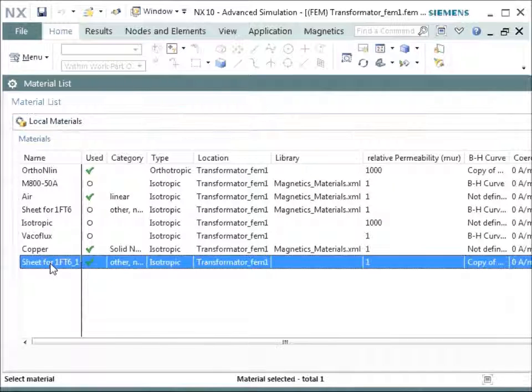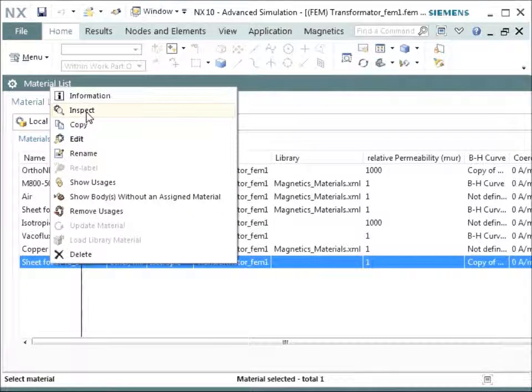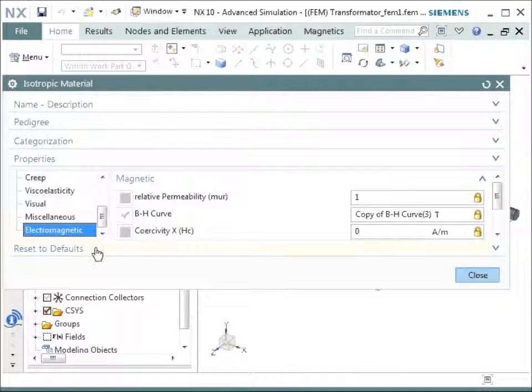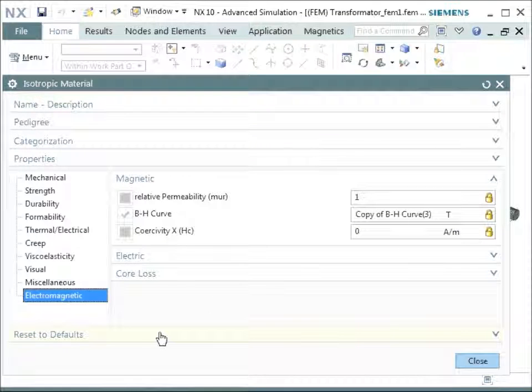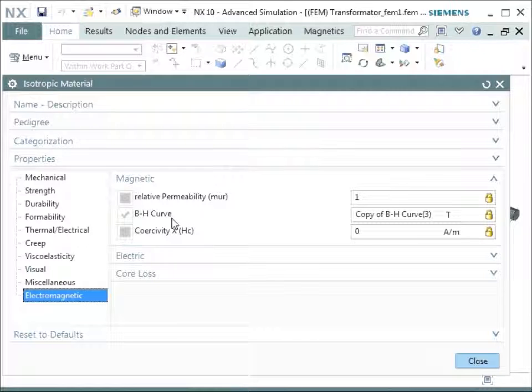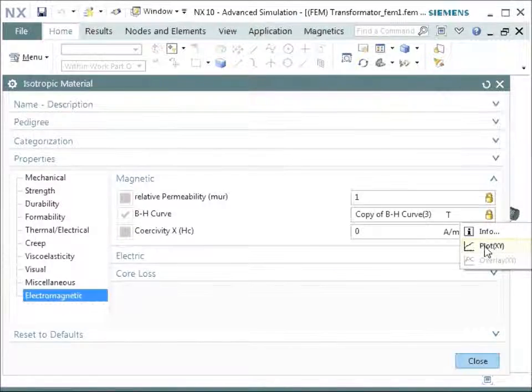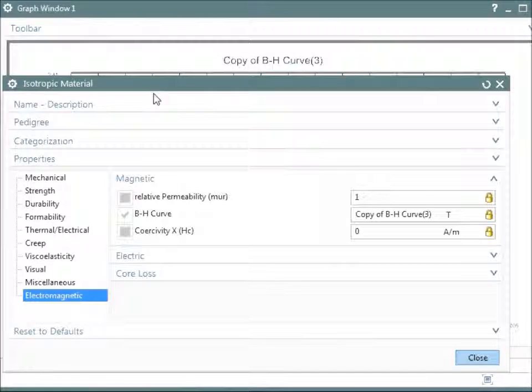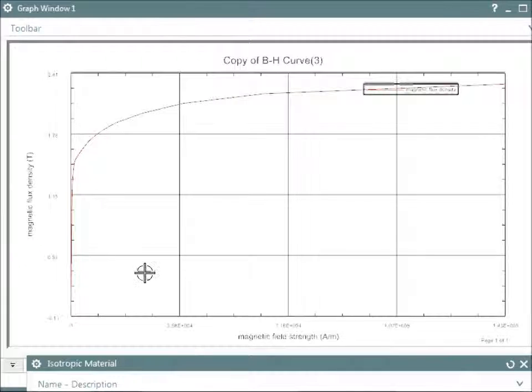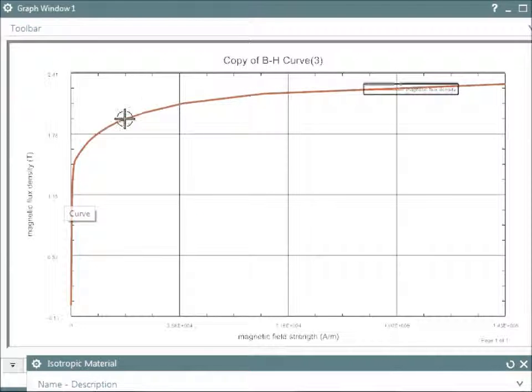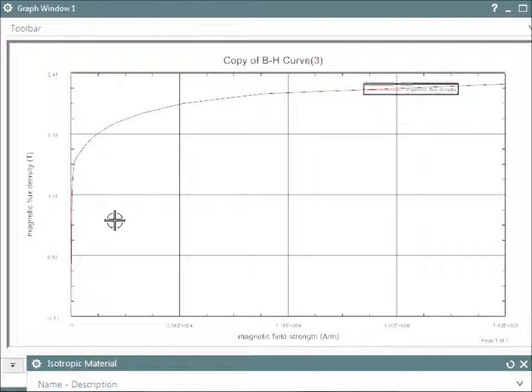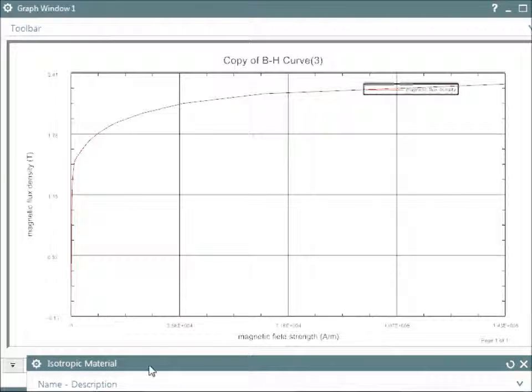So this is the one that we are looking for. Let's inspect this material. We see that this material has electromagnetic properties and many other properties too. We have a BH curve for the saturation. Let's look at the BH curve. Let's plot it here in this little window. You see this is the nice way that the saturation effects are shown with this BH curve. All these effects, these non-linear effects are taken into account in the analysis. This is quite important for the accurate analysis of a transformer.